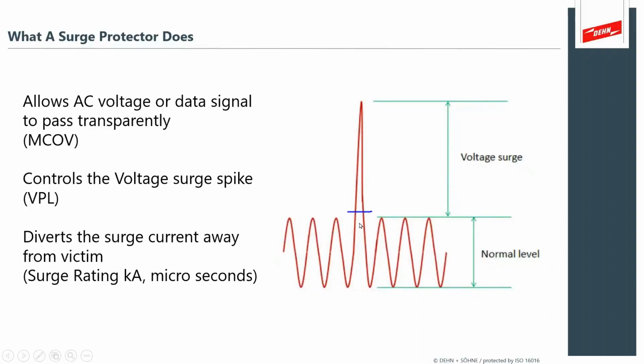And then the other big term you see is the surge current. You're going to divert it away from the victim. And that's essentially the current that is in this top spike, what you're diverting away. There are many descriptions of it in the technical standards. It's rated in microseconds, milliseconds. You have all sorts of different descriptions of it, but it's generally seen as kA in microseconds. That's the market we're talking about.